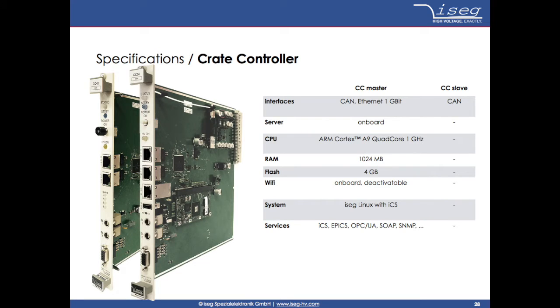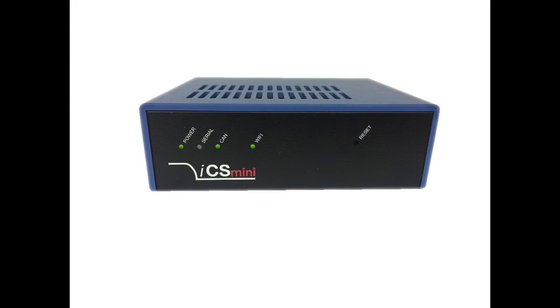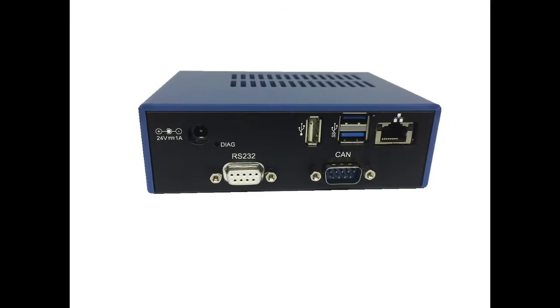Regarding controllers there are two types available: a master and a slave controller. The master controller is equipped with an onboard ICS2 server card, so at least one of those is necessary for a running system. For prior iSEG crate system versions which are already used in the field, it is also possible to update the server functionality with an external ICS2 server system called ICS mini.